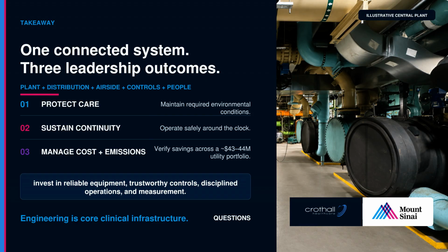The takeaway is simple. This is one connected system, and it produces 3 outcomes. First, protect care by maintaining the environmental conditions required by each clinical and research space. Second, sustain continuity through reliable equipment, redundancy, 24/7 coverage, safe changes, and disciplined maintenance. Third, manage cost and emissions through efficient operation, demand response, utility incentives, approved setbacks and resets, dual fuel readiness, and verified savings. The investment priority is reliable infrastructure, trustworthy sensors and controls, disciplined operations, and measurement. Every energy measure must protect the clinical requirement, preserve reliability, and produce measurable results. We should capture available incentives, but the incentives should support a sound engineering project, not create one. Engineering is core clinical infrastructure. When HVAC performs well, the hospital performs well.